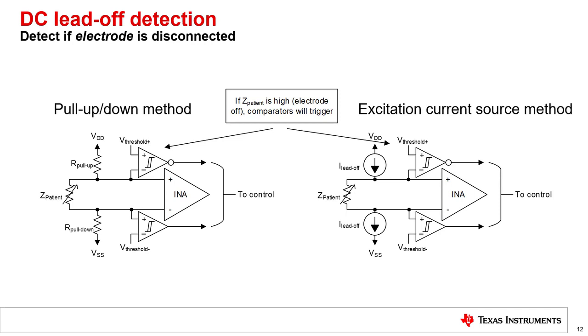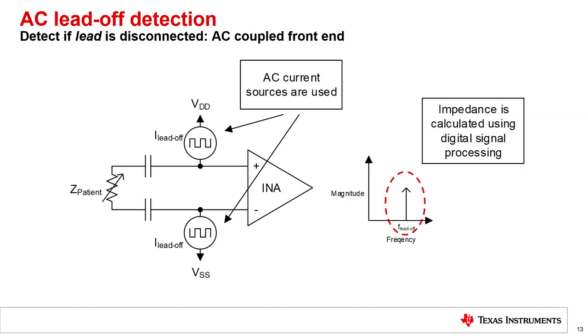On the right we have a current source leadoff detection which works similarly but instead of using a pull-up or down resistor it uses an excitation current source. The same principle applies: when the impedance becomes too large, the voltage at the inputs of the comparators will cause them to trigger, indicating leadoff to the user. Since each INA input is connected to a separate comparator, the status of each individual electrode can be monitored at all times. The output of these comparators can be tied to a microprocessor for instant notification.